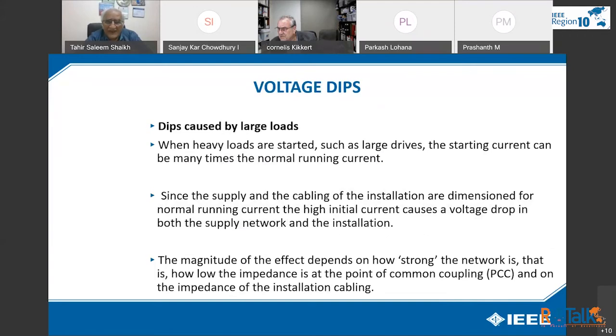Dips caused by large loads occur when heavy loads are started, like large motors, welding, and large drives. The starting current can be many times the normal running current. Since the supply and the cabling of the installation are dimensioned for normal running current, the high initial currents cause a voltage drop in both the supply network and the installation. The magnitude of the effect depends on how strong the network is, that is how low the impedance is at the point of common coupling, and on the impedance of the installation cabling.